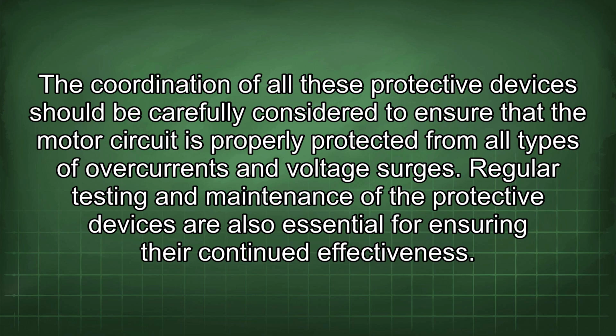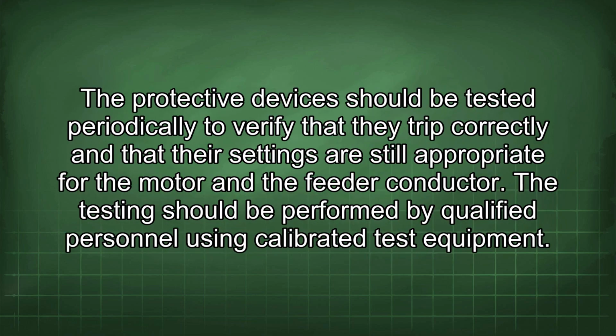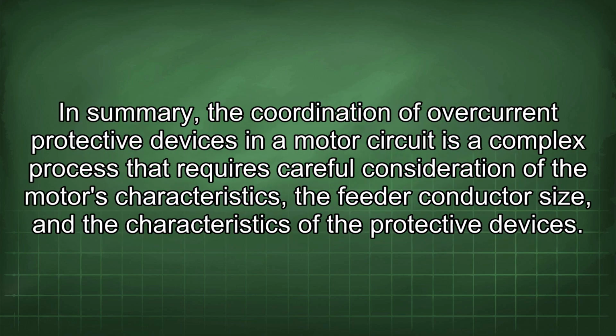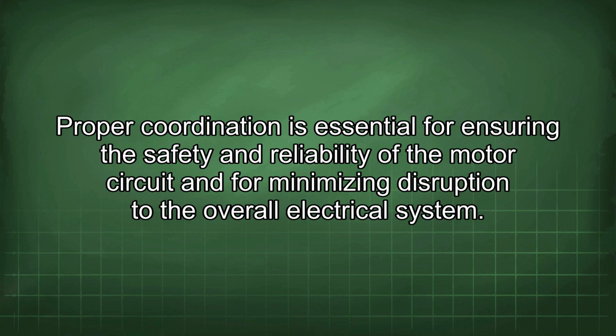Regular testing and maintenance of the protective devices are also essential for ensuring their continued effectiveness. The protective devices should be tested periodically to verify that they trip correctly and that their settings are still appropriate for the motor and the feeder conductor. The testing should be performed by qualified personnel using calibrated test equipment. In summary, the coordination of overcurrent protective devices in a motor circuit is a complex process that requires careful consideration of the motor's characteristics, the feeder conductor size, and the characteristics of the protective devices. Proper coordination is essential for ensuring the safety and reliability of the motor circuit and for minimizing disruption to the overall electrical system.